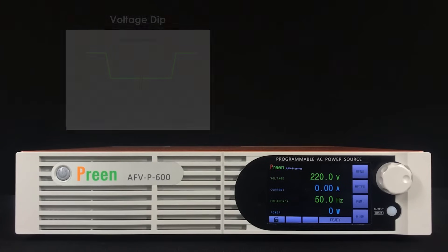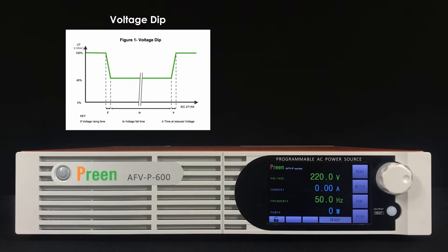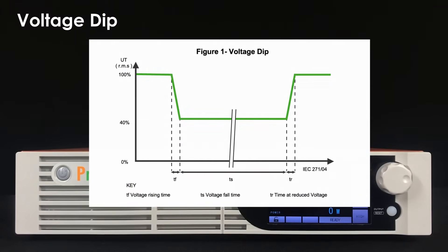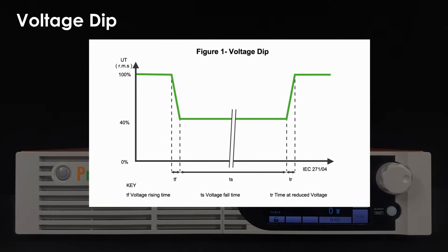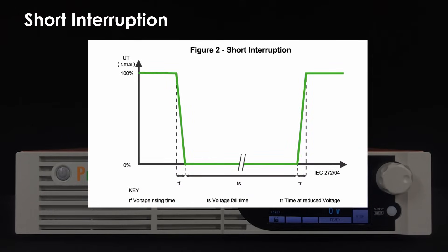We will demonstrate how to simulate voltage dips and short interruptions by using the AFV-P-600 model. A voltage dip indicates a sudden reduction of the voltage at a particular point of an electricity supply system below a specified dip threshold, followed by its restoration after a brief interval. A short interruption indicates a sudden reduction of the voltage on all phases at a particular point of an electrical supply system below a specified interruption threshold, followed by a restoration after a brief interval.